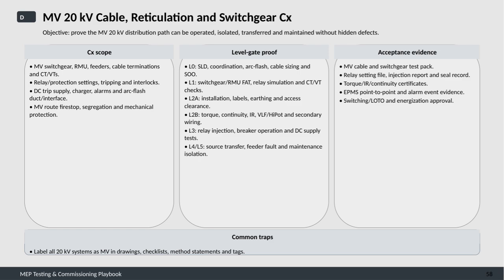For acceptance evidence, it's crucial to have a complete test pack for MV cables and switchgear. This includes relay setting files, injection test reports, seal records, torque and insulation resistance certificates, and evidence from the electrical power monitoring system covering point-to-point checks and alarm events. Formal approvals for switching, lockout, tagout, and energization must also be documented.